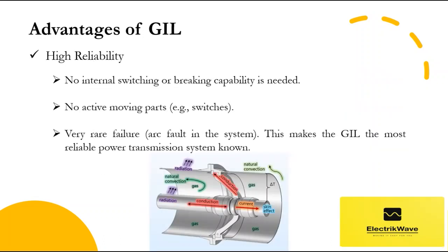GIL has high reliability. The only purpose of the GIL is electric power transmission — no internal switching or breaking capability is needed. Based on this, the GIL can be seen as a passive high voltage gas insulated system with no active moving parts such as switches. Today, more than thousands of kilometers of single phase lengths have been in operation worldwide for more than 45 years. Very rare failures — arc faults in the system — have been observed, making the GIL the most reliable power transmission system known.